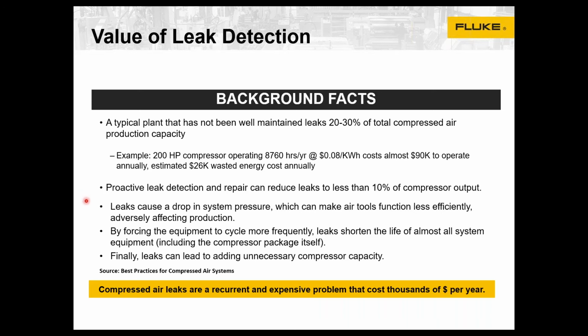There's also other positive byproducts of leak inspection, which you may have production-related issue if you don't have adequate pressure or point of use. If your compressors are running more, cycling more, then it's also going to shorten the lives on that equipment. So there's a lot of benefit. They're recurrent and they're expensive. So it makes sense to have a proactive inspection program. So now let's take a quick look at acoustic imaging. What is that? It applies to leak detection.